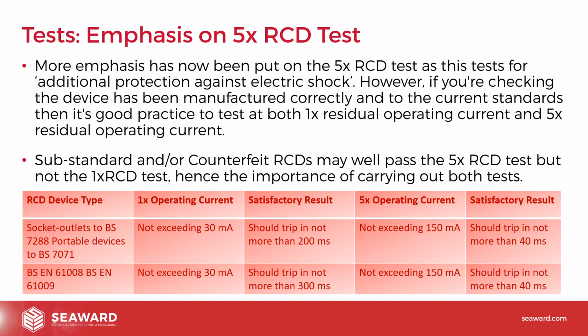The reason for that is you will see a lot of substandard or counterfeit RCDs, or very cheap plug-in RCDs, that may well pass a 5 times test, because you're putting a lot of current through it. You're putting 150 milliamps through, and yes, it passes the 5 times test. But then you do a 1 times test and you find it fails. That's quite common with substandard devices, where they will work at the higher current but not the lower current. So we still think it's important that you test at both 1 times and 5 times.